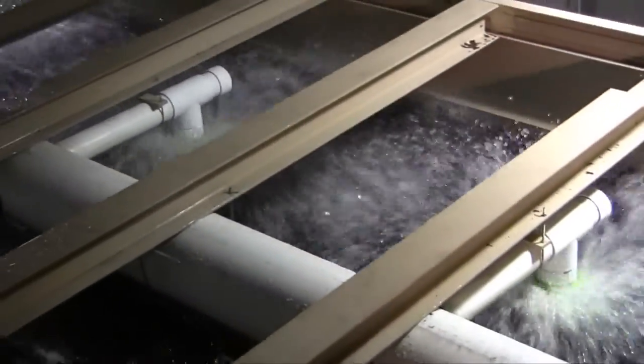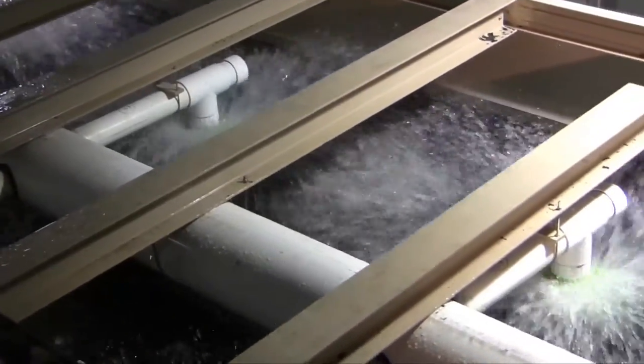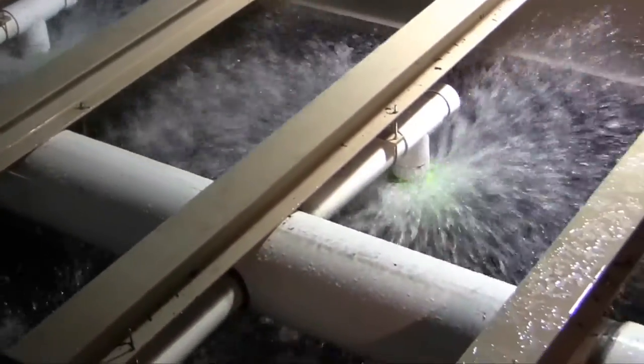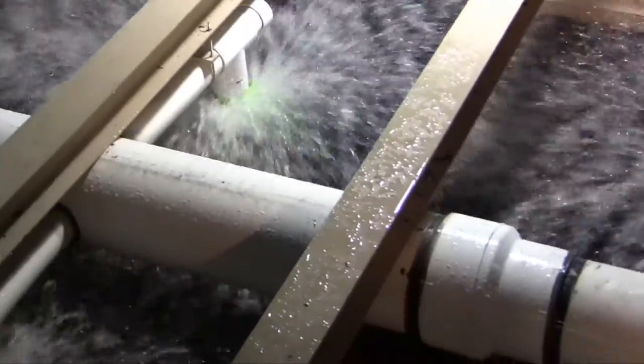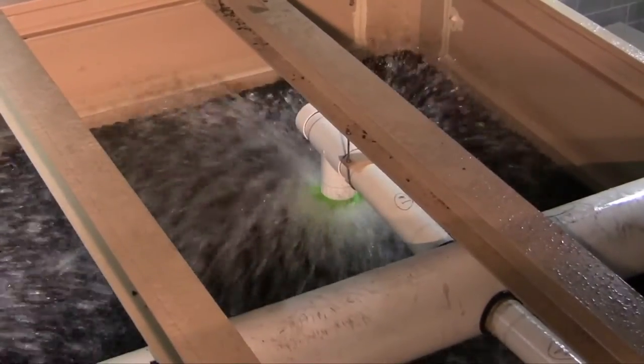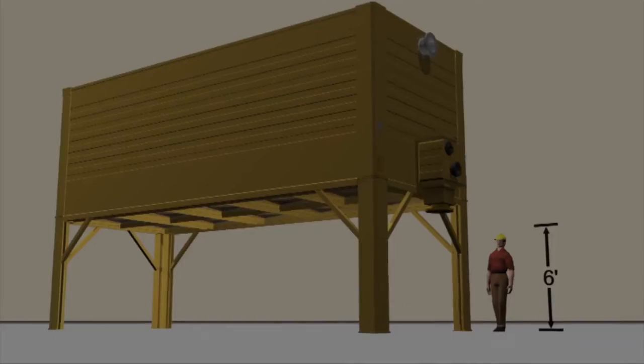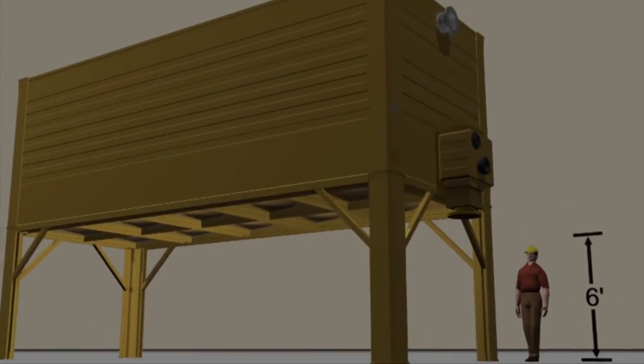This hydraulically balanced square pattern is essential to maintaining a good balance of water and air within your tower. The rotary spray nozzle has an indefinite life expectancy when operated between 100 and 300 GPM. When you inspect them, also inspect the tower's hot water distribution system, which is made up of schedule 40 PVC piping. The pipe connection to the tower's exterior walls may need resealing after several years.